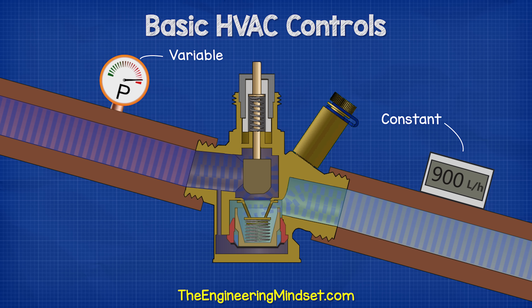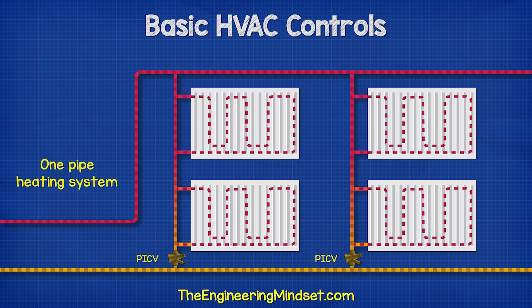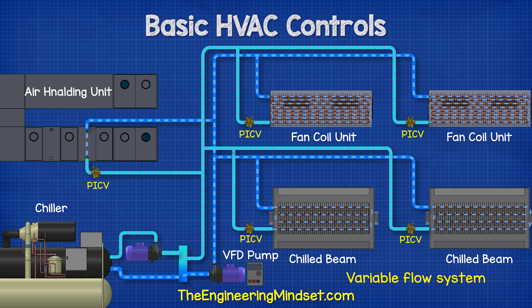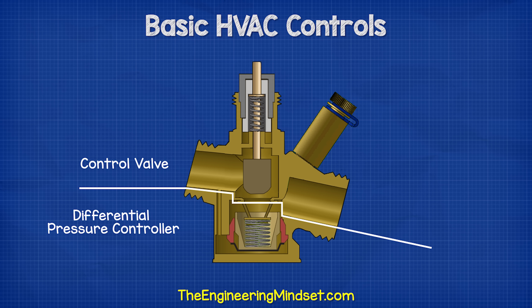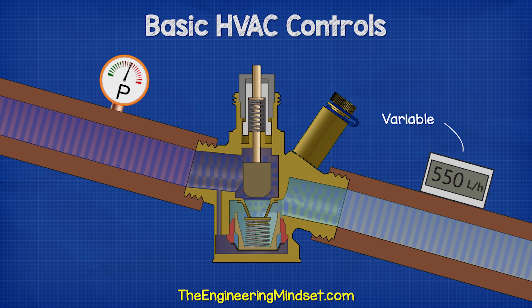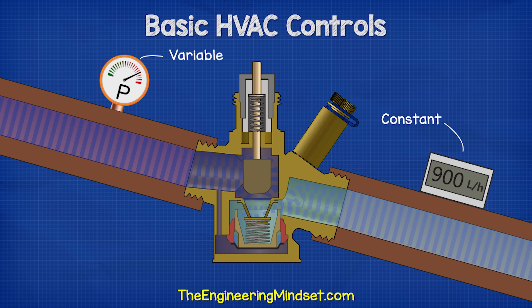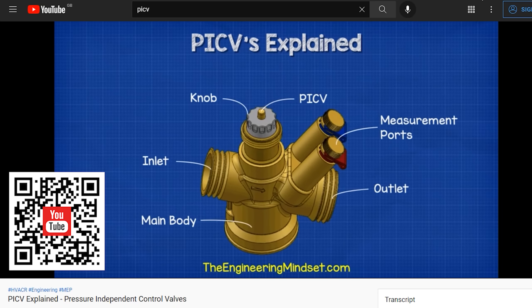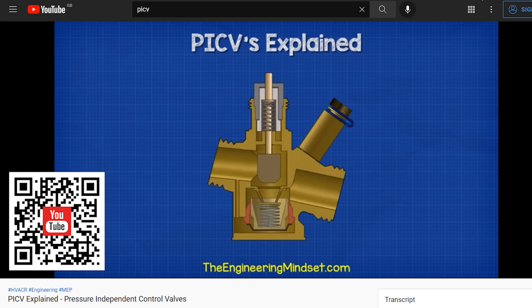Alternatively, we could use pressure-independent control valves. As the name suggests, these valves maintain a constant flow rate through the valve, independent of pressure fluctuations in the system. These are used in heating systems, but also, for example, in a central cooling system in a commercial building to control the flow rate through fan coil units and air-handling units. These are basically multiple valves combined into one design: the lower part maintains a constant pressure difference across the valve, and the upper part regulates the flow rate. We have covered how pressure-independent control valves work in detail previously, and I'll leave a link in the video description below.